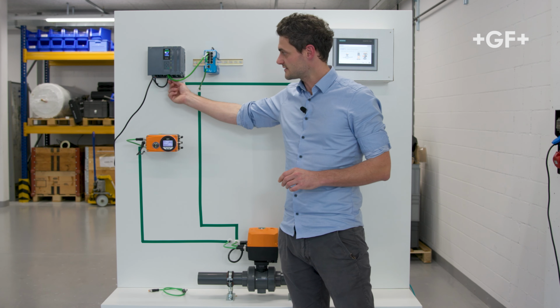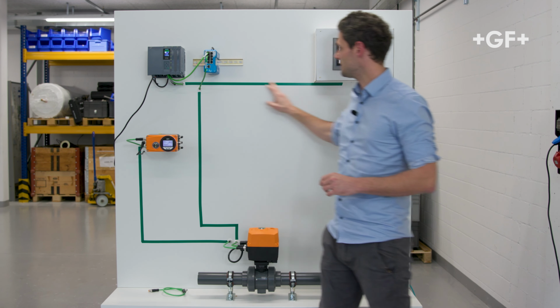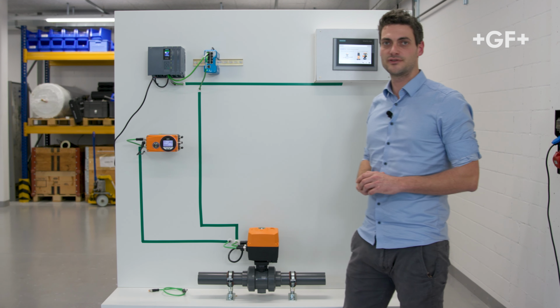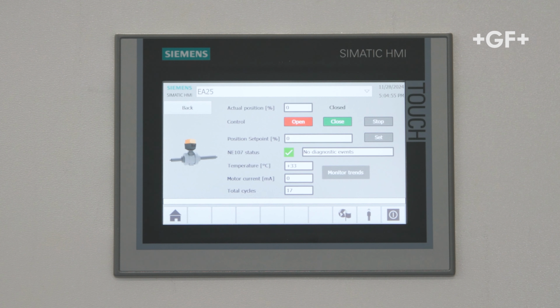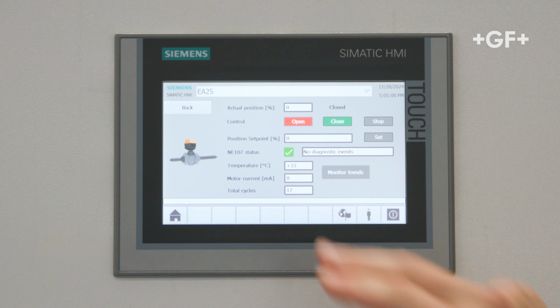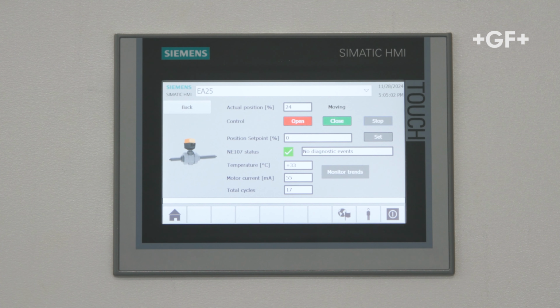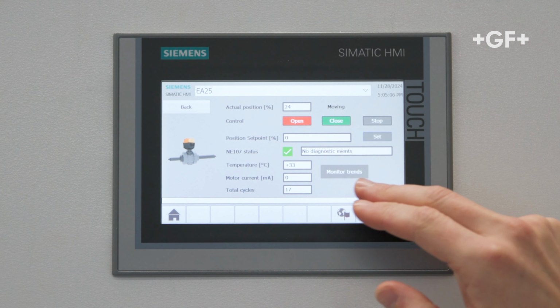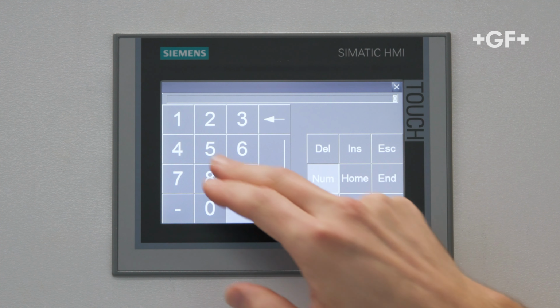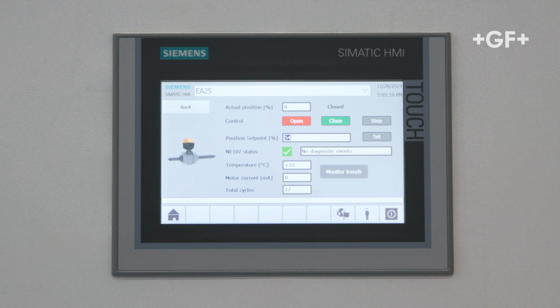So here, via the second port of the PLC, we have connected an HMI. Let's take a look at which data is accessible. Besides the normal device functionalities, like opening and closing the valve, with the Ethernet actuator it's even possible to use the so-called positioner mode, which means I can bring the device to a certain percentage value between the open and closed position, often used for dosing applications, for example.